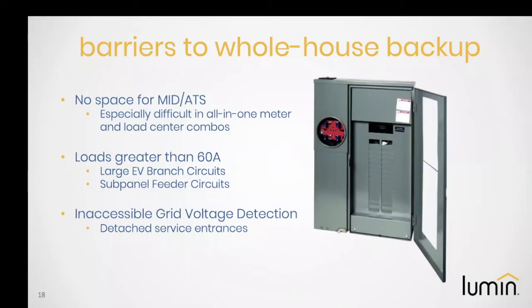Second, as Kevin mentioned earlier, Lumin has a 60 amp circuit amperage limitation. So in some homes, we'll see circuits that are too large to connect to the Lumin panel. Some common examples of these might include larger electric vehicle branch circuits, where multiple charging outlets are being fed by a single circuit. Another example would be subpanels. 100 amp subpanel feeder circuits are also common. And if there are no large loads on that subpanel, if it's all lights and outlets and relatively small ones, it's probably not problematic.